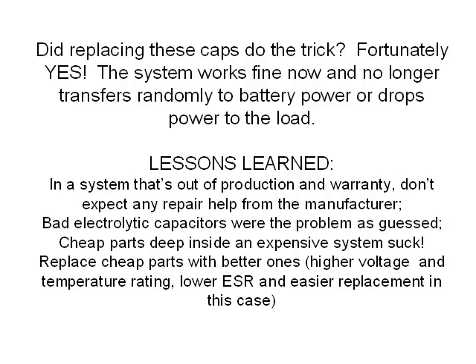I hope this is helpful to you, even if your UPS model is different. Just remember that electrolytic capacitors are a common weak link in all circuits that have been in use for a number of years. If you have further questions, please leave feedback, as some of the methods used here might be useful as separate videos in the future.